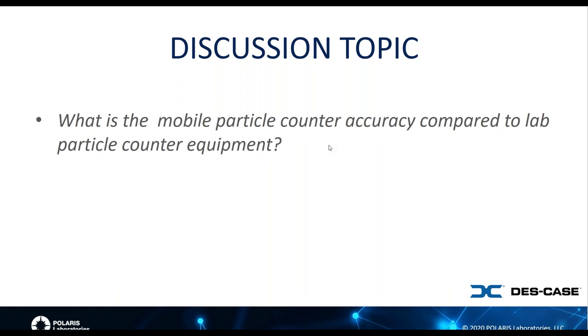There is a role for mobile particle counters in the field, but it is a trending tool. It tells you whether the oil is getting cleaner or dirtier. But I would caution anybody using a mobile particle counter in the field, and I'm thinking about sensors in particular, to be cautious. You can get handheld laser scatter particle counters that you can take out in the field and plug into an instrument. They do give you an accurate reading, but I'm assuming the question here is about a particle count sensor as opposed to a true laser particle counter. They have their place. I don't think anybody on this panel is suggesting that they replace high quality lab analysis. Definitely not. As far as accuracy, the laboratory method is more precise than any mobile particle counter.